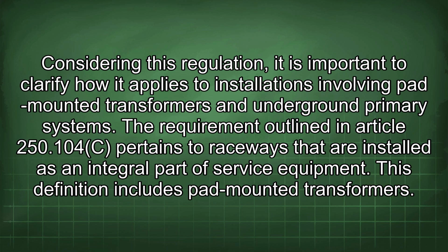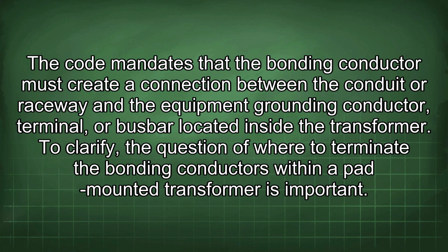The requirement outlined in Article 250.104(C) pertains to raceways that are installed as an integral part of service equipment. This definition includes pad-mounted transformers. The code mandates that the bonding conductor must create a connection between the conduit or raceway and the equipment grounding conductor, terminal, or busbar located inside the transformer.